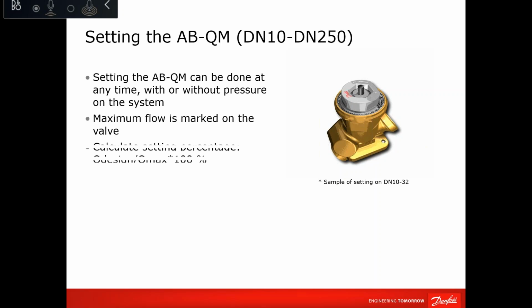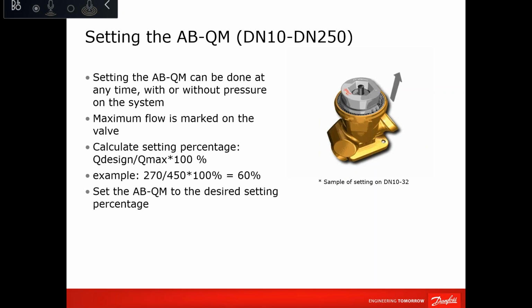So the maximum flow is marked on the valve. If we take your design flow or equipment flow divided by the valve flow, you will end up with a percentage. In our example, 270 liters per hour divided by 450 liters per hour, 60%. You just need to pull this gray part up, clockwise to reduce and anti-clockwise to increase, go to 60%, lock it down, and the balancing is done. It's very simple. Nothing should be done, no calculation, no KV, no tables, nothing. And the setting is done. This is the balancing part.